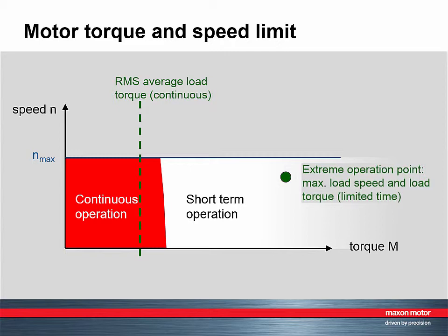The speed limit of Maxon motors corresponds to the upper limit of the operating range diagram. However, it is essentially the required torque that defines the motor size. We have to select a motor that, on average, can produce the necessary torque. Hence, we need a motor with the nominal torque larger than the RMS average load torque. Short load peaks, as during acceleration, may be located in the short term operating range.